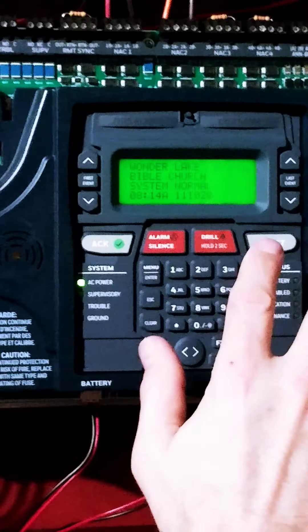Leave it like that. Right now you're not monitored, so you can go ahead and reset it after you reset the pull station — I'll show you how to reset a pull station. I have a key in the door and I'll leave a key in here for resetting pull stations if someone pulls one. You reset the pull station, then come down and reset the system and it will go back to all systems normal.